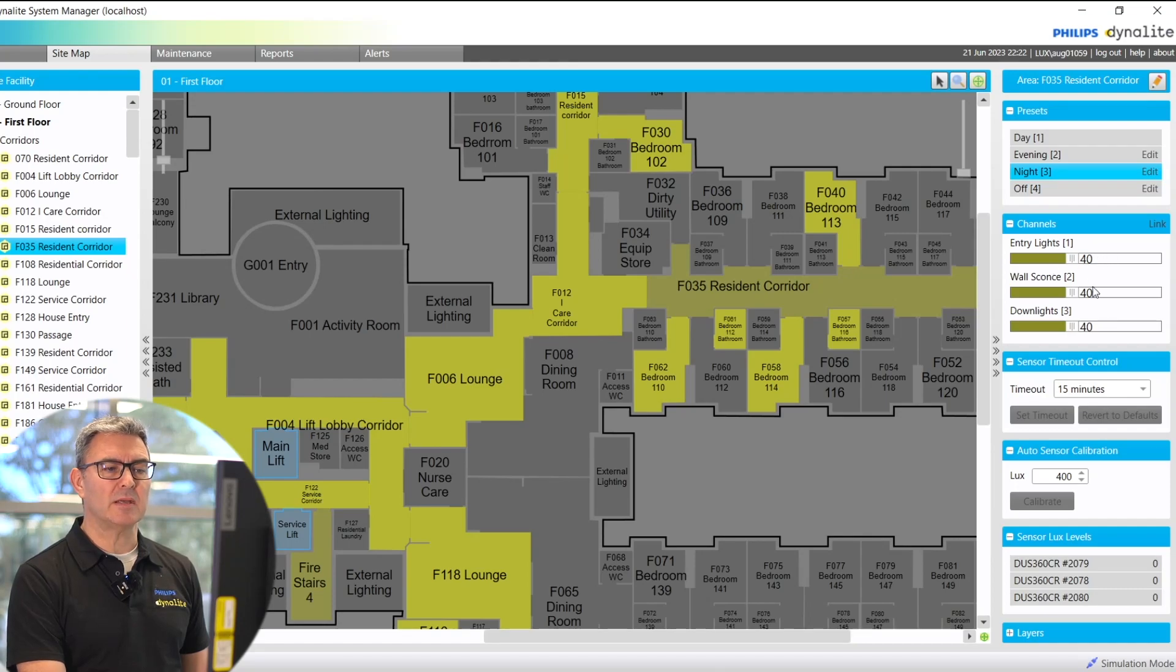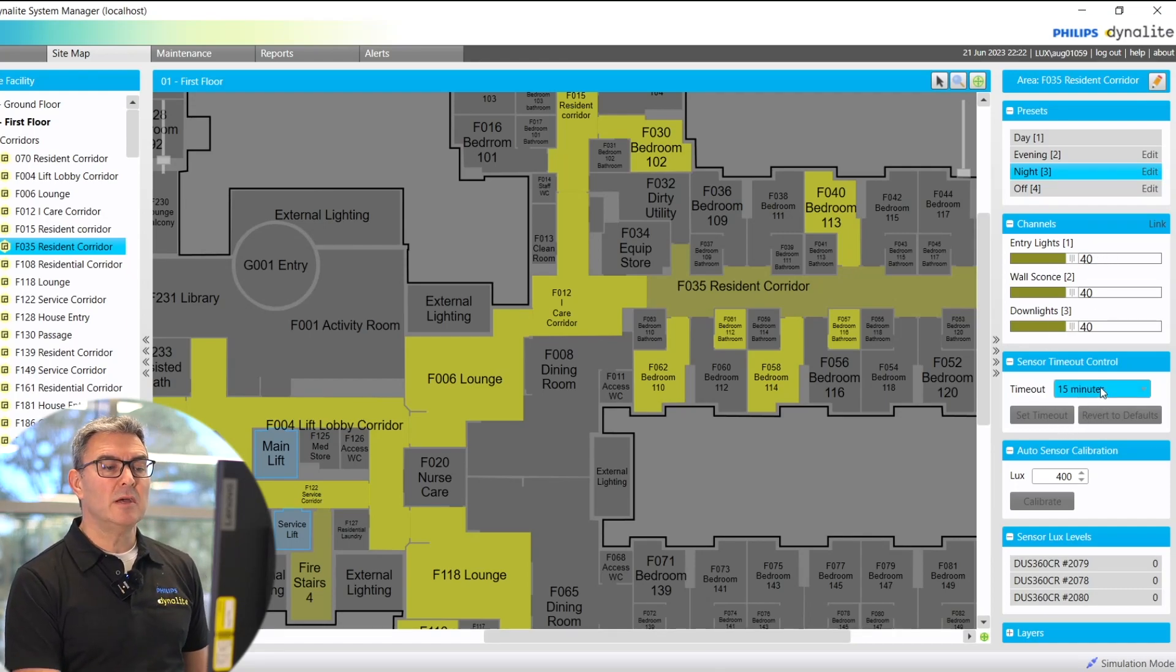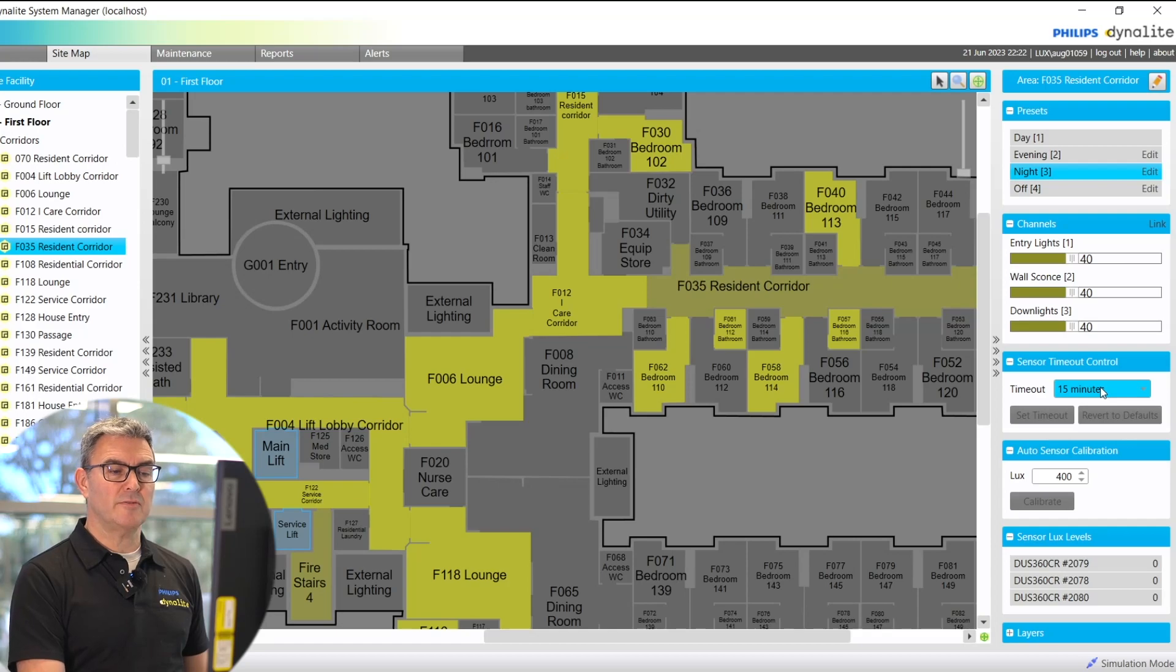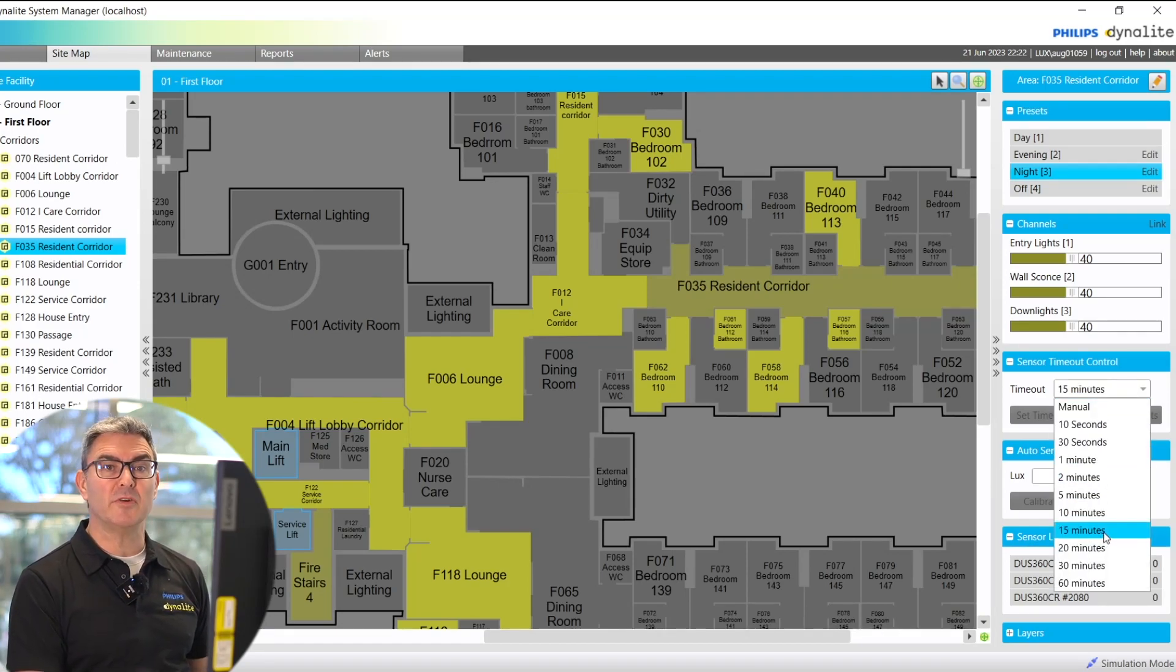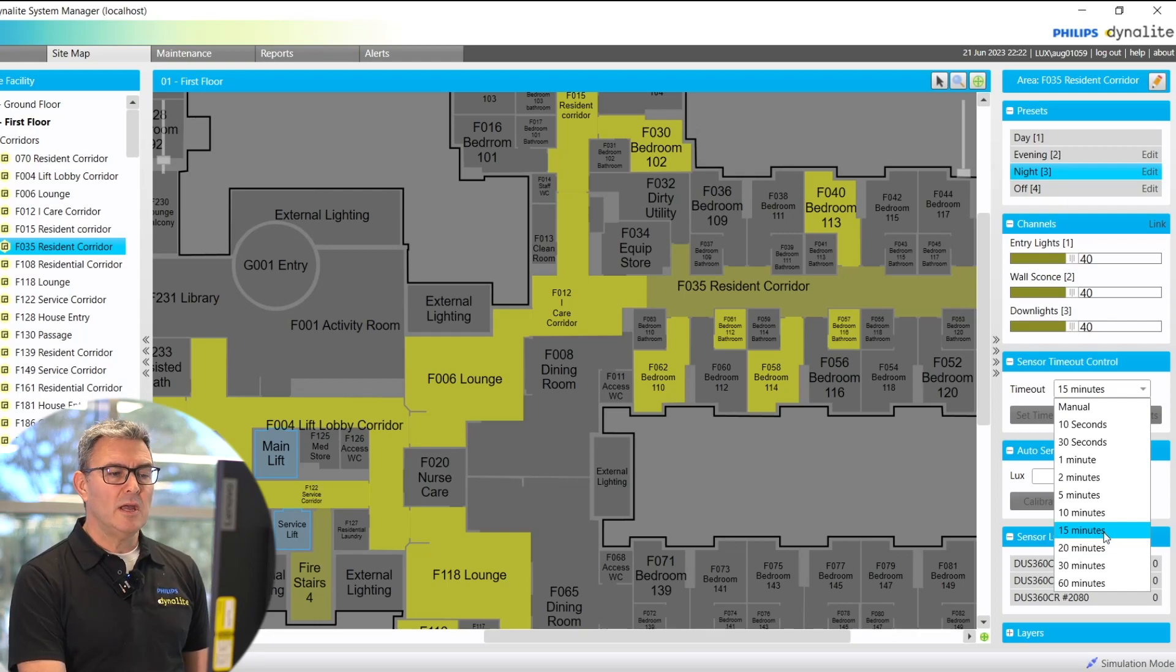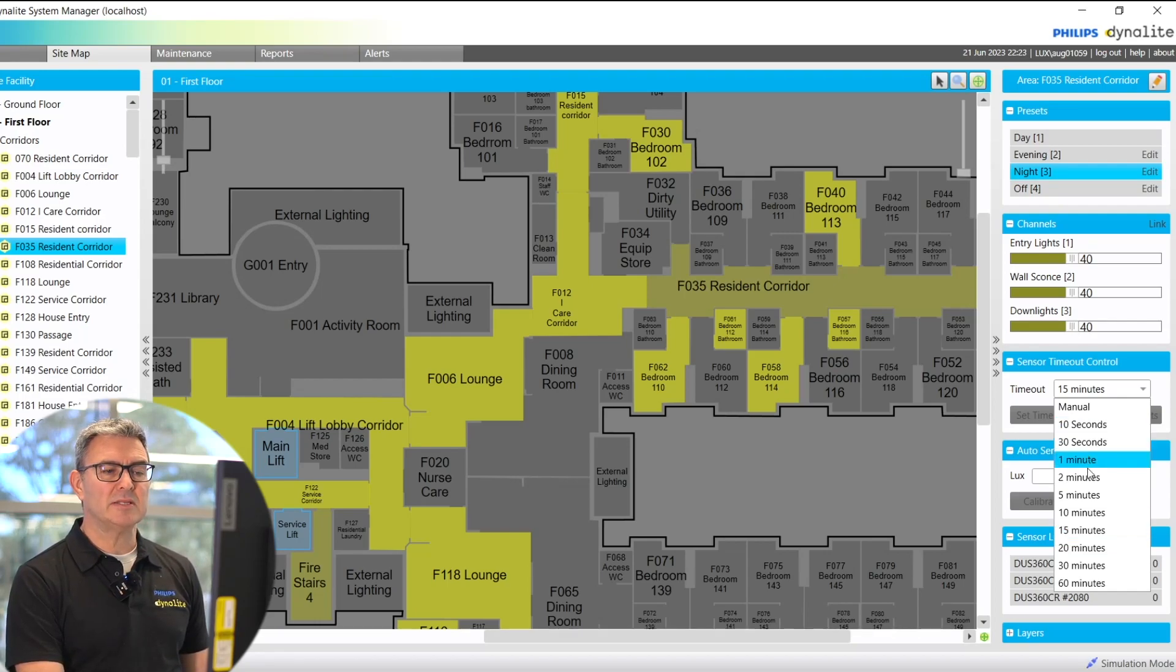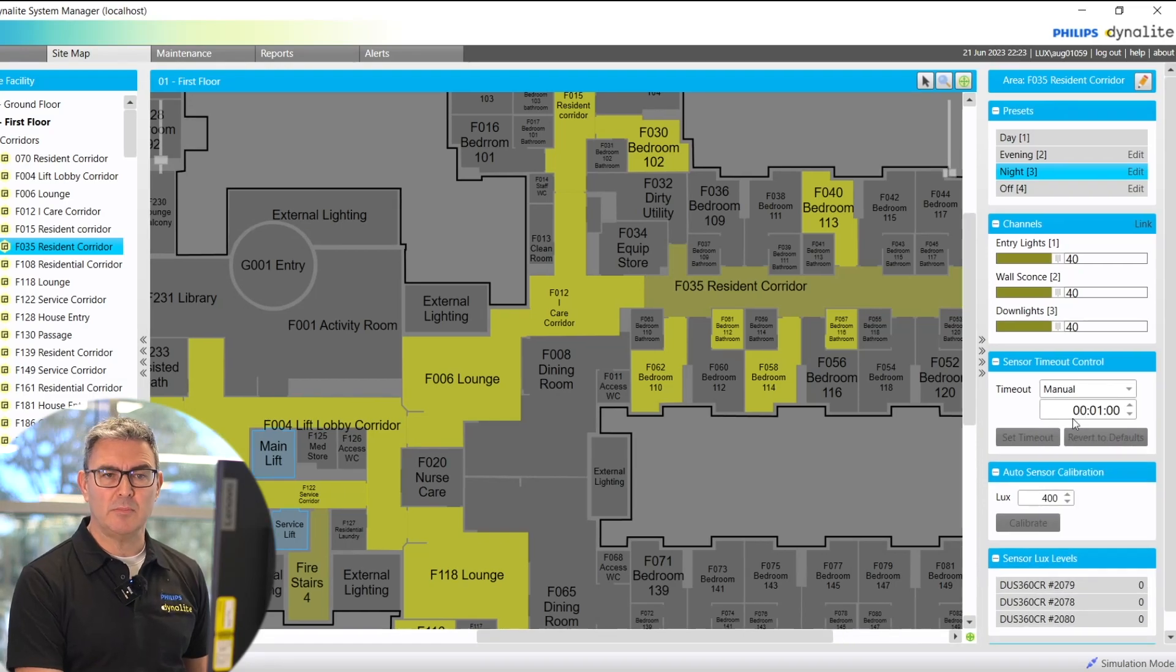I can adjust sensors if there's a sensor in the area. I can choose from a range of timeouts. These are the amount of time the area is unoccupied before the lights go to a standby state. If the amount of time I want is not there, I can go manually and put it in manually.